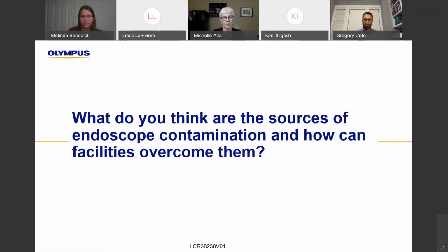To give you an example, the European guidelines actually do require regular monitoring of the final rinse water, because it's a parameter that can often go unrecognized for very long periods of time. I myself have been involved with a couple of facilities in our province that had problems with that. It arises because the submicron membrane filter—the 0.2 micron membrane filter—if it has micro breaks in it, you may not even see a big pressure drop, but sometimes you'll see a pressure drop of the water coming in, and that should be a red flag that the membrane filter may not be functioning properly.